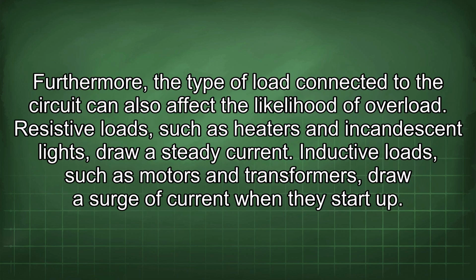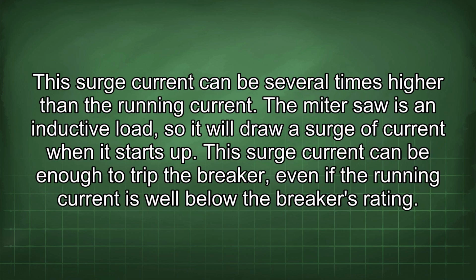Furthermore, the type of load connected to the circuit can also affect the likelihood of overload. Resistive loads, such as heaters and incandescent lights, draw a steady current. Inductive loads, such as motors and transformers, draw a surge of current when they start up. This surge current can be several times higher than the running current. The miter saw is an inductive load, so it will draw a surge of current when it starts up.